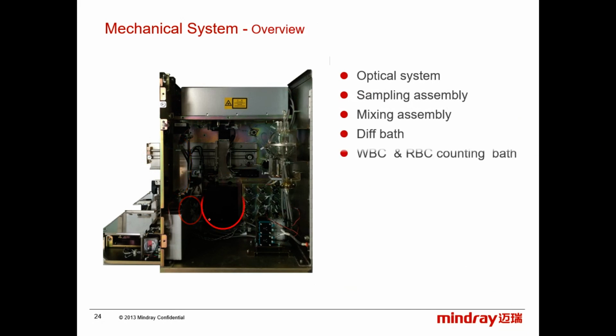Diff bath, WBC and RBC counting bath. As you see here, they are shielded. We use a Faraday cage here, isolated, because we use the impedance principle. So it is very sensitive to electrostatic interference, okay? Because the impulse sizes are very small, so it is easily interfered.